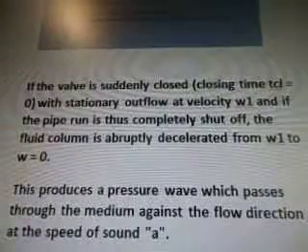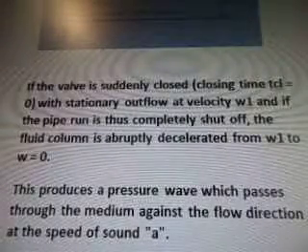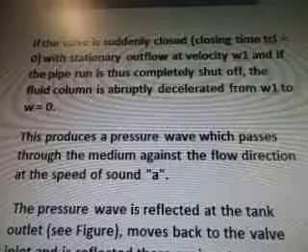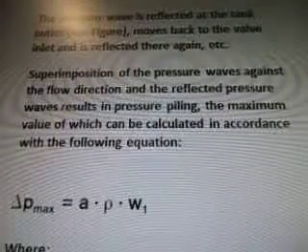If the valve is suddenly closed — closing time TCL equals zero — with stationary outflow at velocity W1, and if the pipe run is thus completely shut off, the fluid column is abruptly decelerated from W1 to W equals zero. This produces a pressure wave which passes through the medium against the flow direction at the speed of sound A. The pressure wave is reflected at the tank outlet, moves back to the valve inlet, and is reflected there again. Superimposition of the pressure waves against the flow direction and the reflected pressure waves results in pressure piling, the maximum value of which can be calculated in accordance with the following equation.